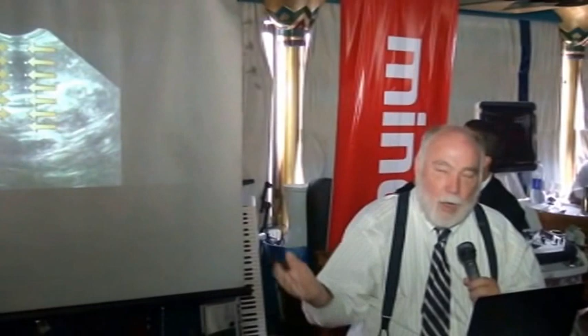What is happening here? What is that? This is a broken transducer. Transducers are very delicate equipment, and if you let the transducer drop on the floor, then the elements here are no longer attached, and they create a shadow like this. And that shadow is very typical because you will see the same shadow from image to image. So you do one patient, you do the second patient, the shadow remains in the same place. So be careful with the transducer, always reattach them where they're supposed to be. Other example, you see the same shadow no matter where I put the baby.